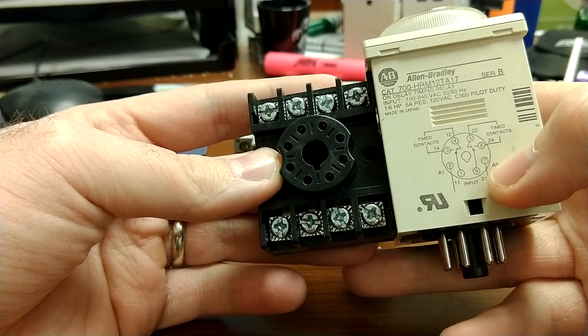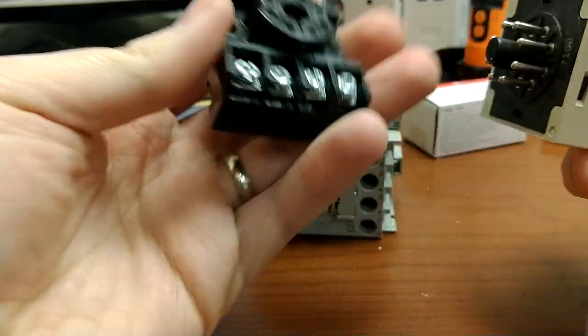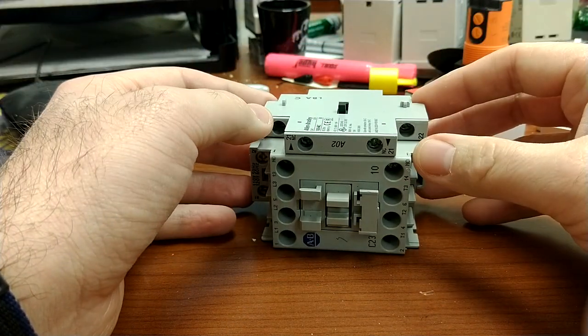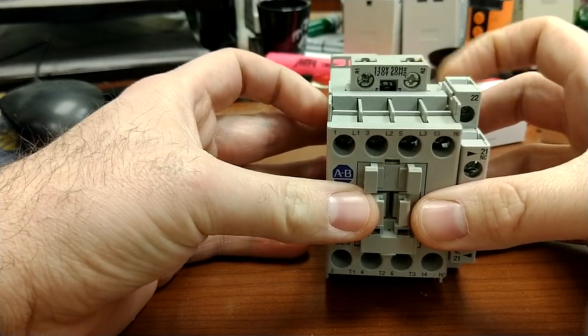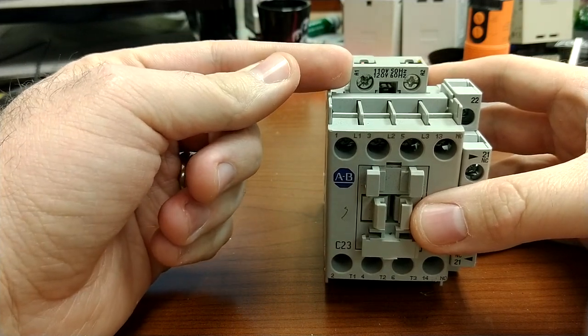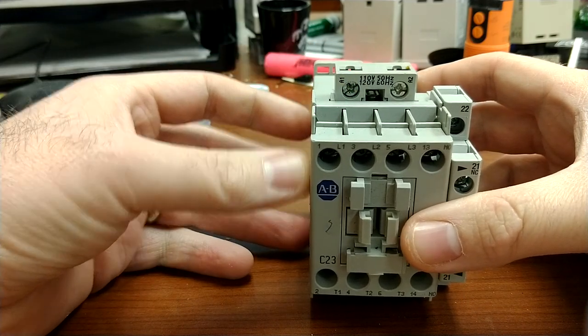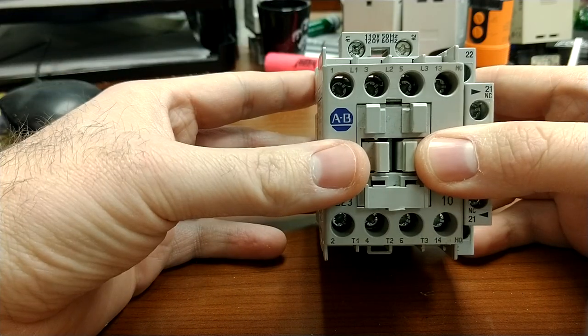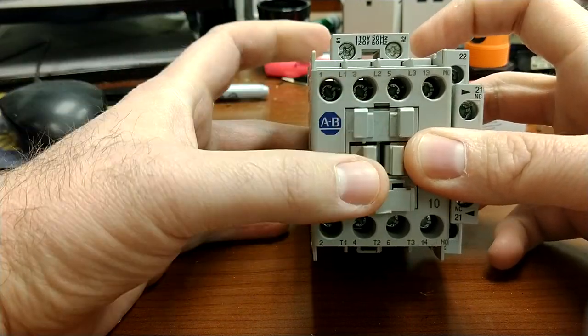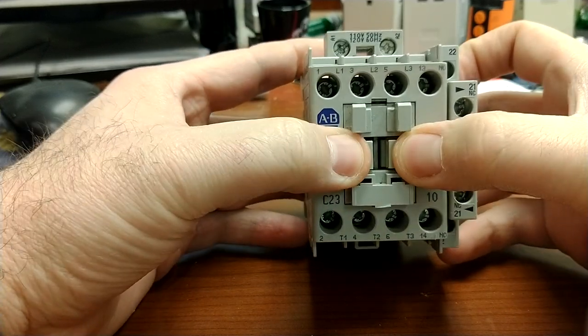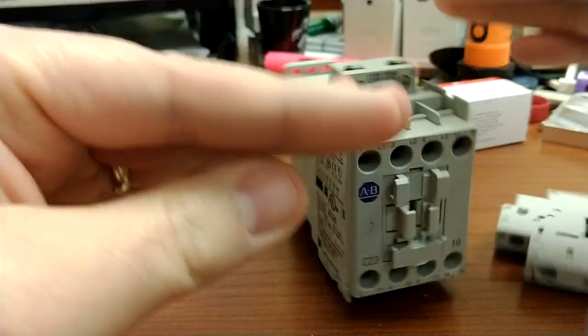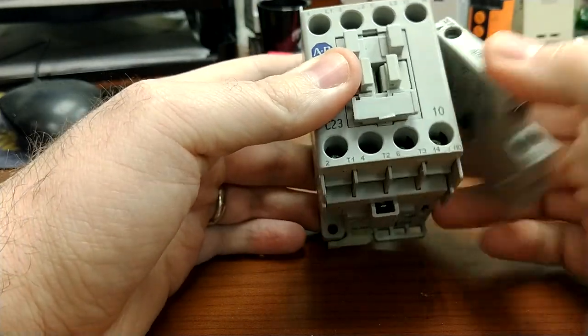Contactors work very similar to that, except instead of having this being able to be separated and wired universally like this, because you're usually controlling higher voltage, and usually you're using it to turn on and off a three-phase motor, they're usually set up in a fairly rugged setup like this, but if you take a close look, you can see here would be A1, A2, and clearly labeled would be the voltage that this coil can provide.